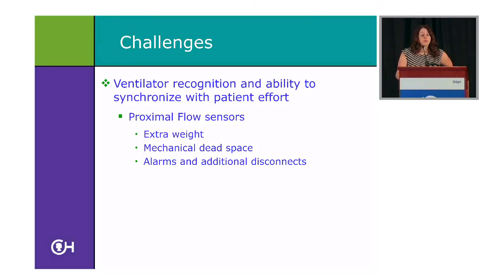Proximal flow sensors help a lot, so that the sensing and delivery of breaths and all the measuring of all the dynamics that we're getting is happening right here at the airway. Our problem with those is they add extra weight, they add extra dead space, and there can be a lot of alarms and additional disconnects that occur because of having to do maintenance on our proximal flow sensors. If you're giving aerosolized meds, if you have an extraordinary goopy kid who's coughing up a lot of secretions, all of those things can cause problems with your flow sensors.